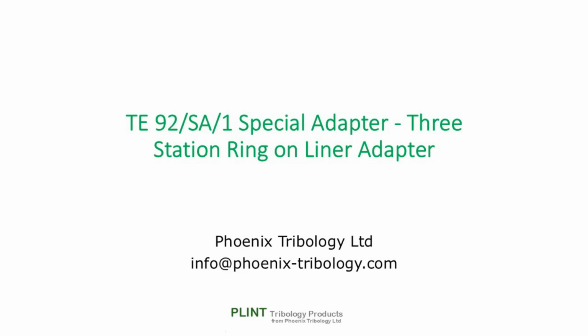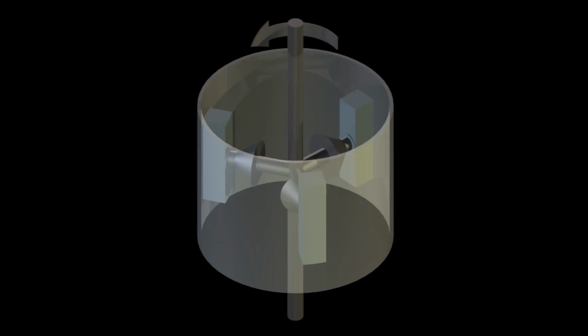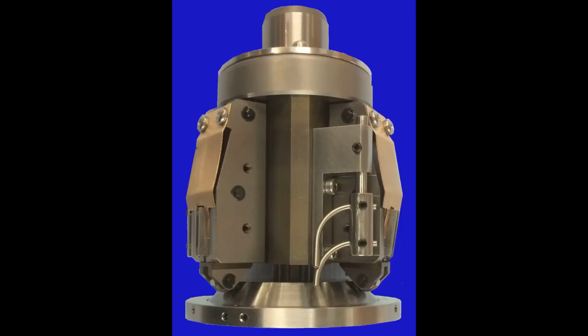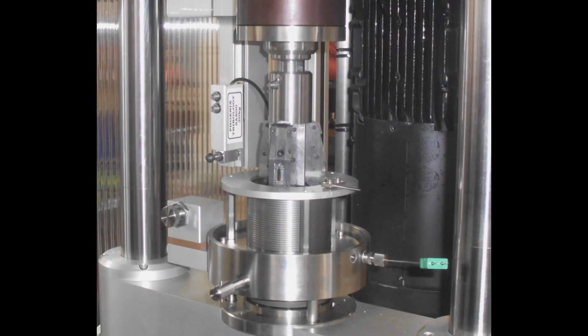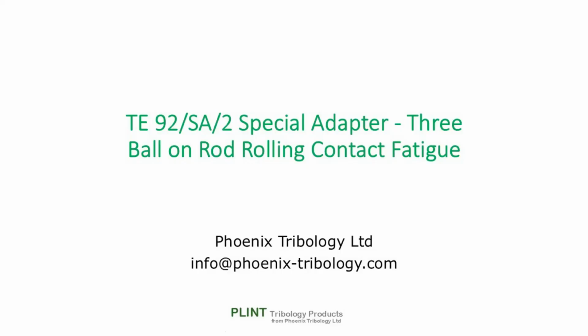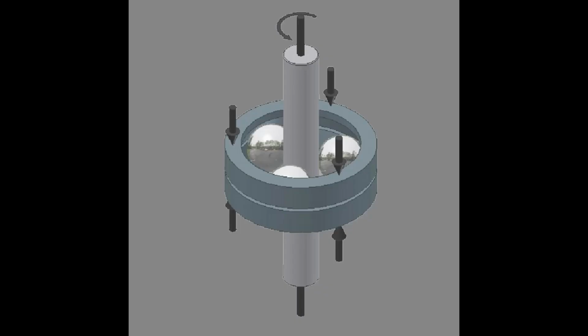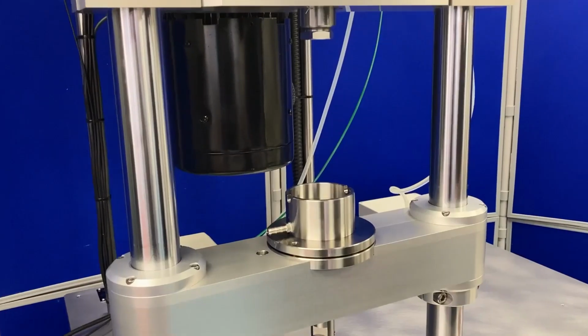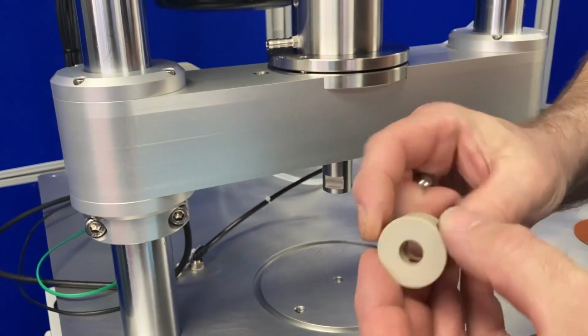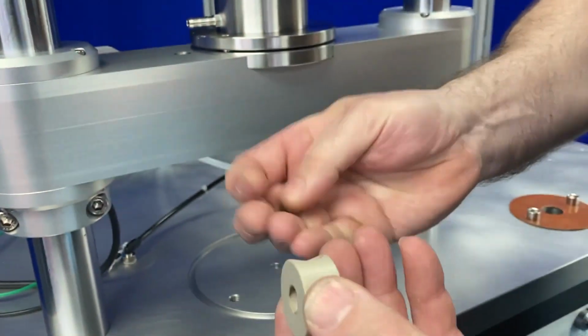A range of more specialized test adapters are available, including a 3-station ring-on-liner adapter, in which ring sections are loaded radially against the inside of a section of cylinder liner. The 3-ball-on-rod rolling contact fatigue adapter allows rolling contact fatigue tests to be run on rod samples of bearing material.